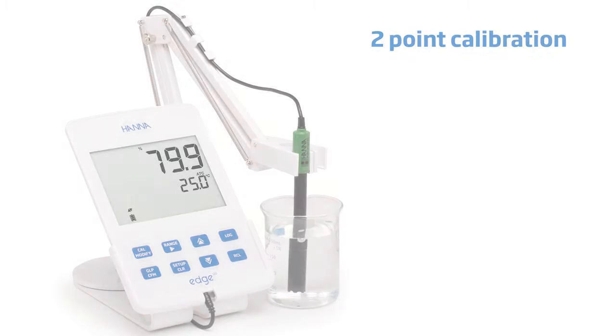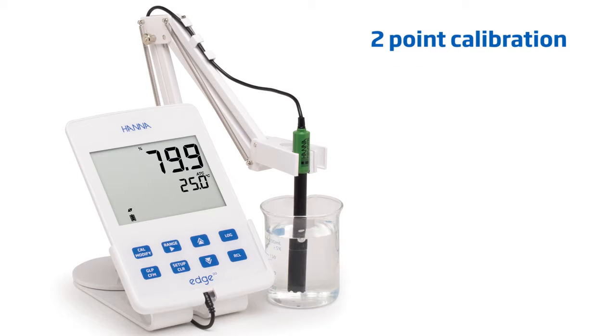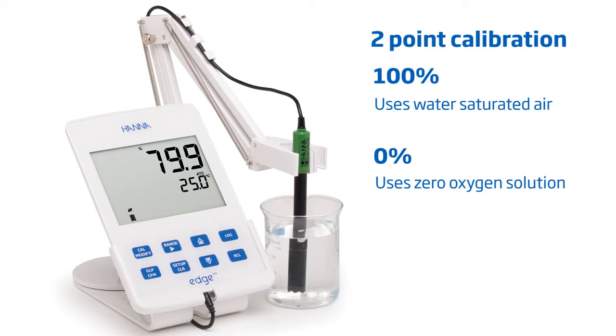Edge meters are capable of calibrating at up to 2 points, 100% and 0%. The 100% point uses water-saturated air. The 0% point uses zero oxygen solution. We'll demonstrate both methods with a 2-point calibration.